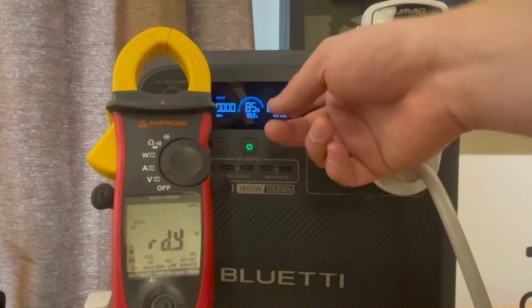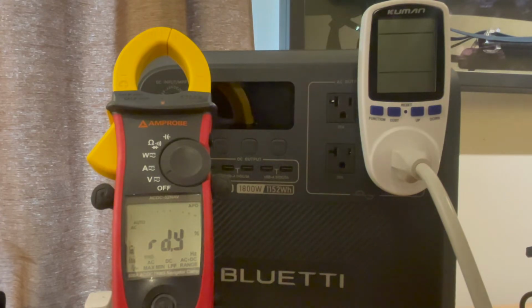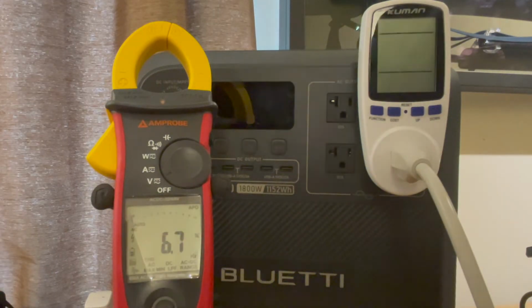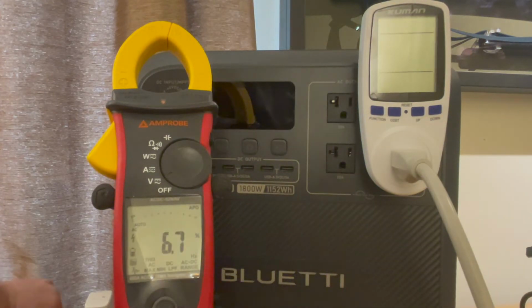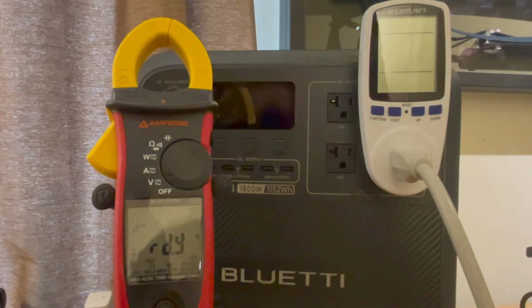Okay, AC output port test. So I've got a couple things going on here. First, I've got just a watt meter, just so you can tell the difference between what this one says and what that one says. This is a total harmonic distortion meter, that's going to tell us how quality the power is. Lower numbers are better. Just to show you, this is the other end of that meter, and I'm going to plug that into my Pacific Gas and Electric utility power here to show you what it says. We are at 6.7% harmonic distortion. Typically 5% or under is the target goal, most devices work until about 8. So 6.7 is what I get out of the wall, so you guys have a reference point.